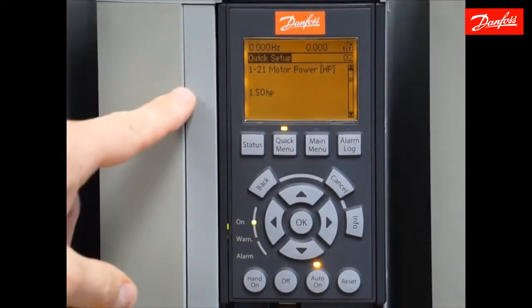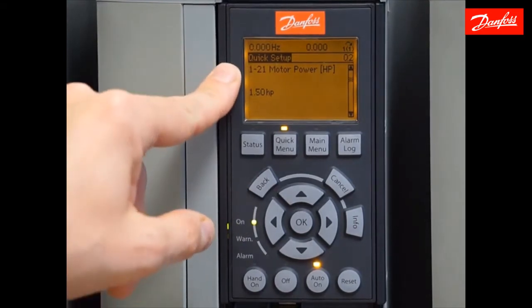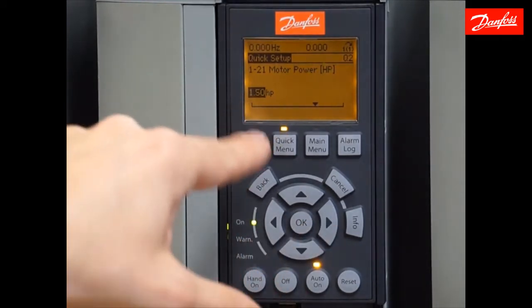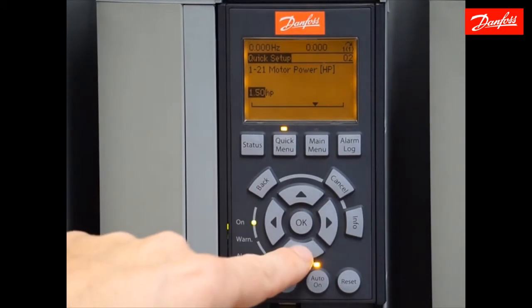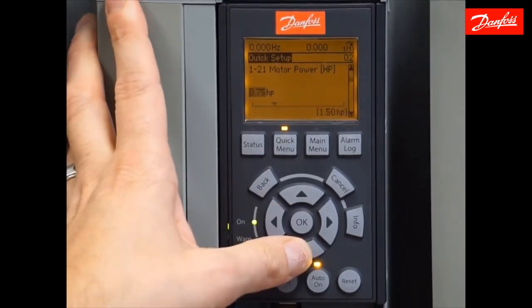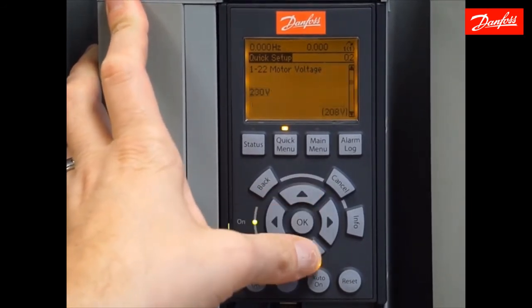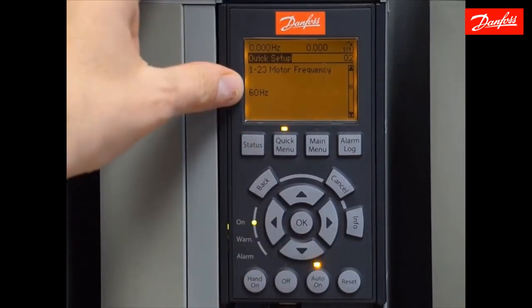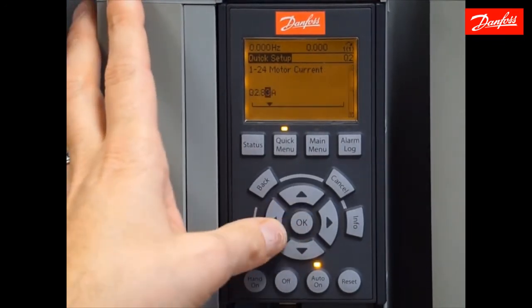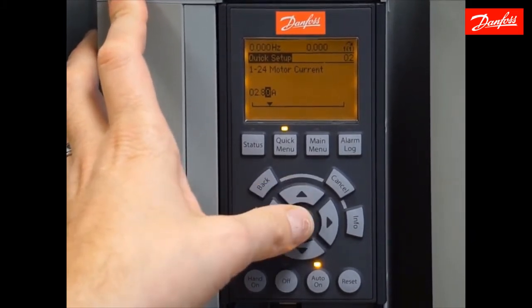The next five parameters are associated with the connected motor, so I'm going to enter my motor nameplate data. Parameter 121, motor horsepower — press OK, it highlights the value, and I can use the up and down arrows to move to the next logical sizes. I have a one and a half horsepower motor, so I'll accept that. Next, motor voltage — I have a 230 volt motor connected. Then 60 hertz, which is automatic based on the North American change. Moving to motor current, I'll use the left and right arrows to adjust to 2.9 amps — got that directly off my motor nameplate.